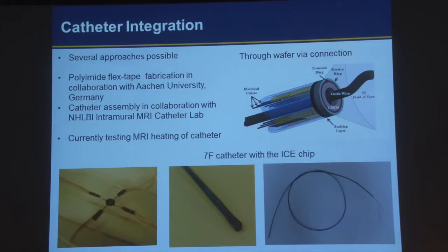And we recently started collaborating with an intramural lab at NIH who are actually developing MRI compatible catheters. So they actually built a catheter for us. And that's kind of a segue to our MRI compatible imaging systems. They're using all MRI compatible materials for the manipulation of the catheters and the catheter body itself. Right now, we are testing these in terms of heating under MRI, so what kind of thermal issue it will generate with those kind of conductors under MRI.